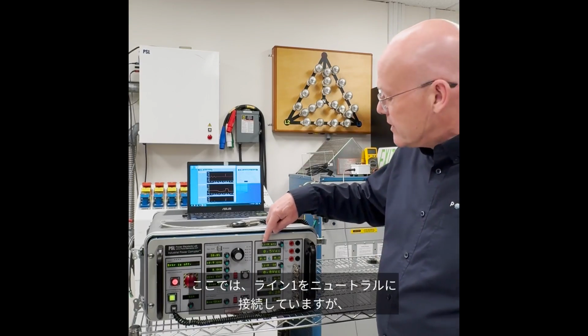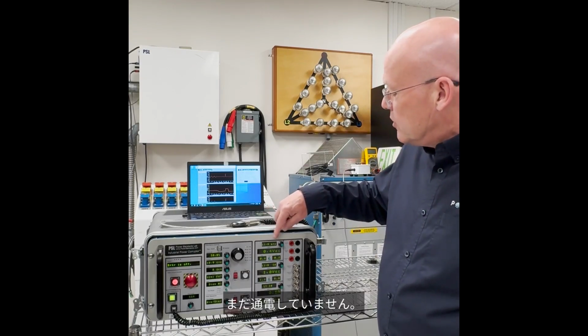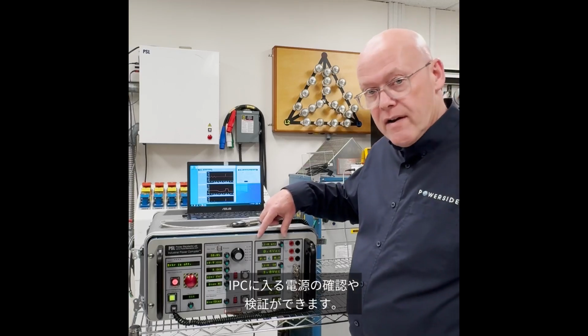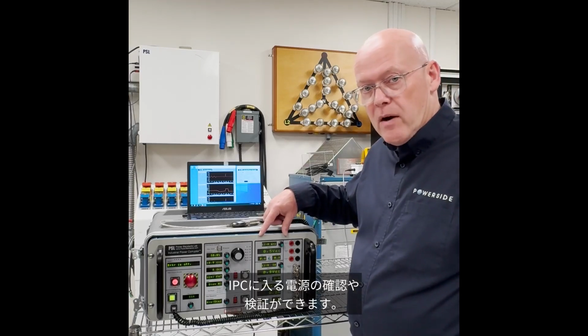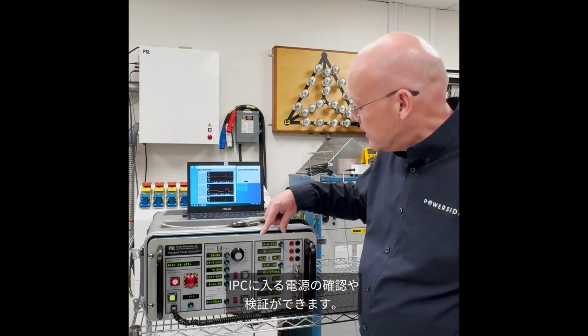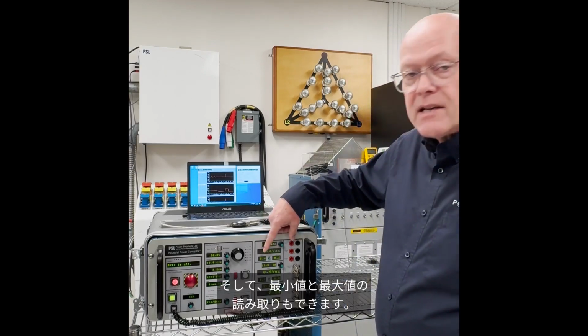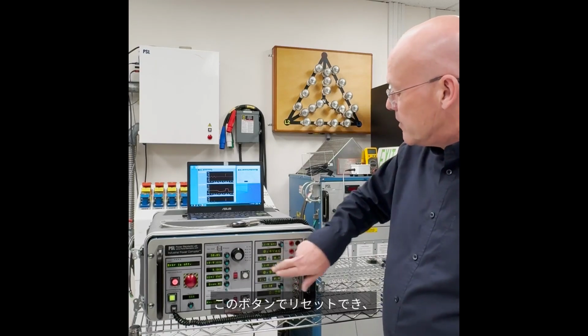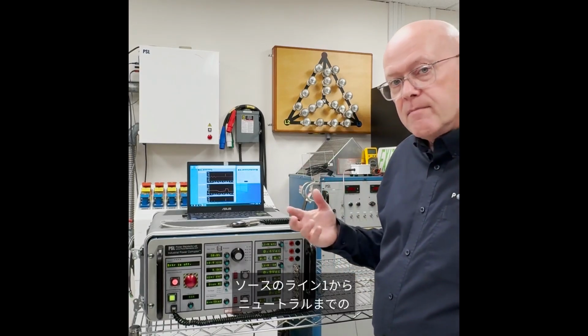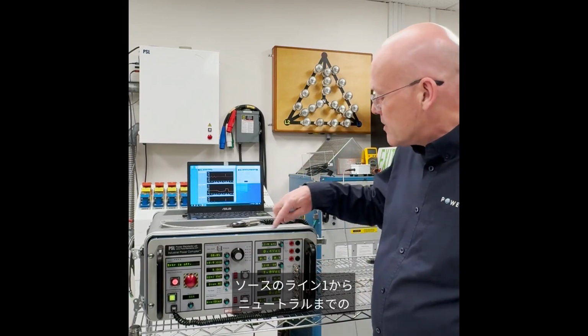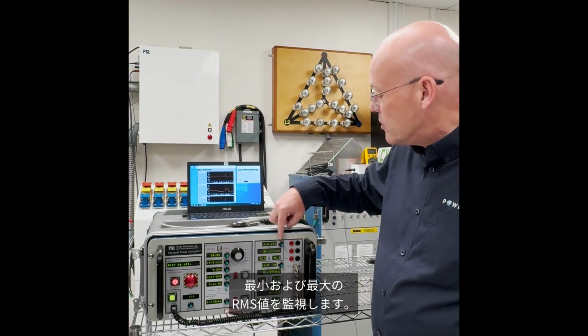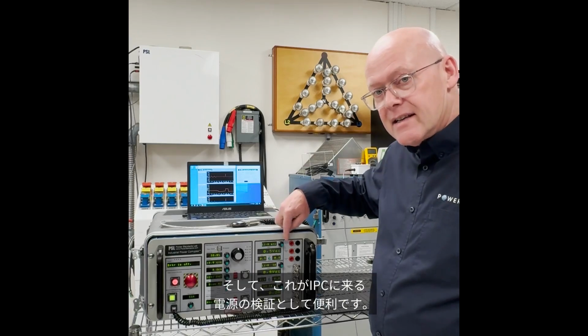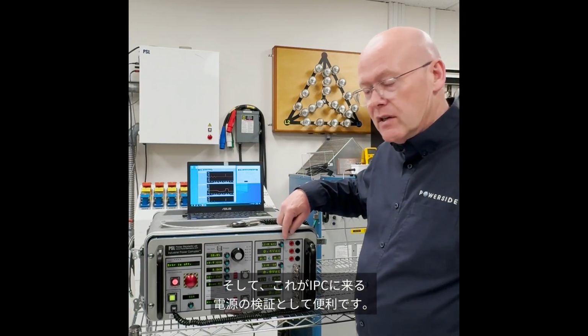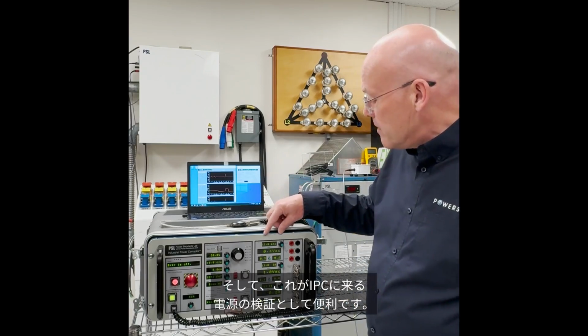We're not energized yet, but this gives you an indication or a verification of your power supply coming into the IPC. And you have minimum and maximum readings as well that you can reset with this button that actually monitor min and max RMS values for line 1 to neutral on the source. It's handy to have this as a validation of your power supply coming to the IPC.